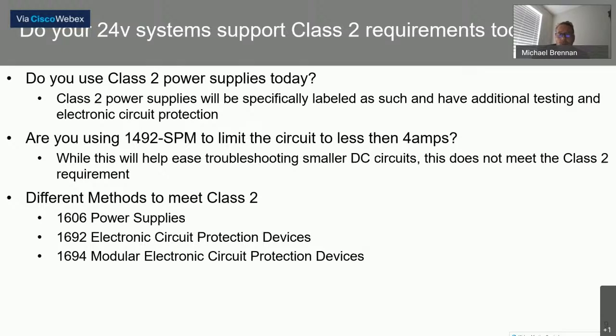You'd have to have an individual Class 2 supply for each one, and that can end up being a little bit cost prohibitive. So having multiple SPMs is easier to troubleshoot because the DC circuits are smaller, but this does not meet the Class 2 circuit requirement. So the different methods that you would use to meet that Class 2 requirement would be specific 1606 power supplies that are rated as such.